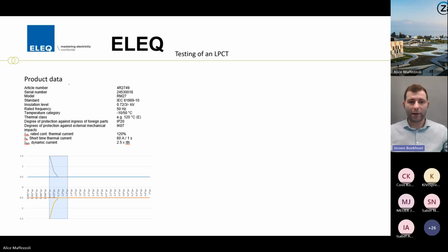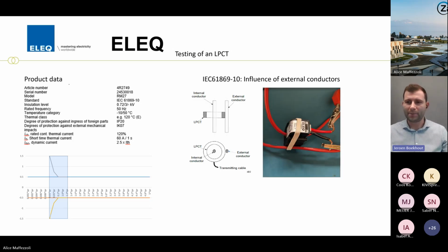So if you look into the testing of this product, we designed the product according to -10. There's a very interesting point and one major difference between the -2 and the -10, and this is the -10 influence of external conductors. In this test, it's specified that you need to have a conductor of the same size at a 90-degree position from the secondary leads with the same amount of rated current. And then the product is allowed to deviate by 1/3 of the norm-specified ratio error when introducing the external influence.